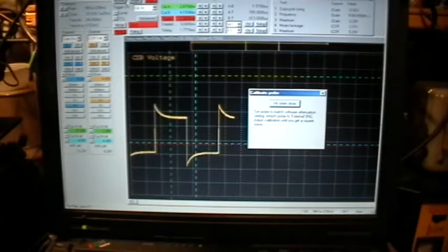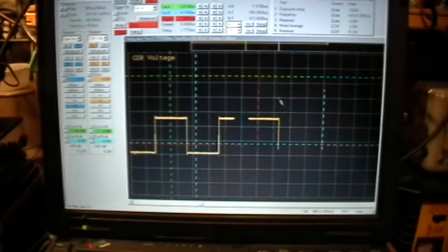Now, I think you can tell that if your probe is badly uncompensated, like this, or like this, your readings are going to be affected. Any computations that you make from an uncompensated or uncorrected probe, those readings are going to be in error. Okay, so there we go. Hit done when done. So we're done.